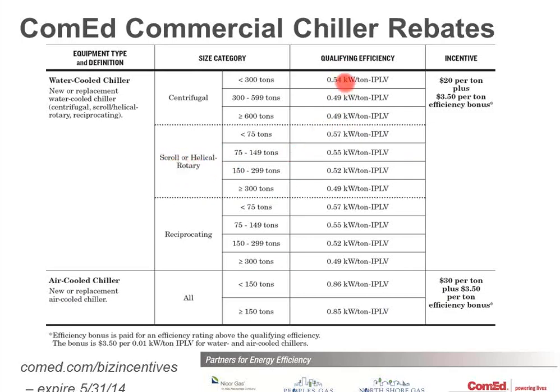They give you a minimum efficiency, and then the lower you can get below that number with your actual machine, the bigger the rebate you get. So it's $20 per ton plus a $3.50 bonus for every 0.01 kW per ton better you do. The kW per ton is IPLV, which is part load. There's nothing that is triggered off of full load because full load hardly ever happens and it's basically irrelevant. So it's all based on part load efficiencies here. And the better you do, the more money you'll actually get. So it's kind of a whole tiered system.